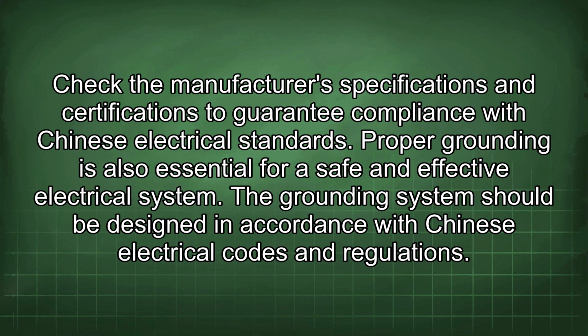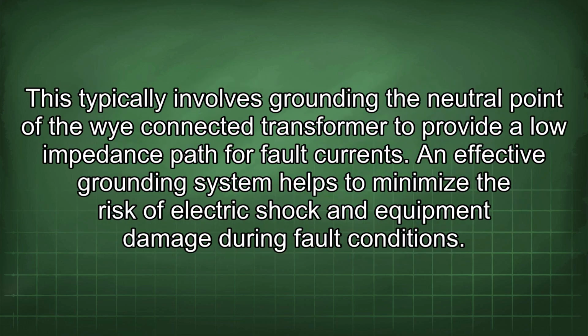Proper grounding is also essential for a safe and effective electrical system. The grounding system should be designed in accordance with Chinese electrical codes and regulations. This typically involves grounding the neutral point of the Y-connected transformer to provide a low impedance path for fault currents. An effective grounding system helps to minimize the risk of electric shock and equipment damage during fault conditions.